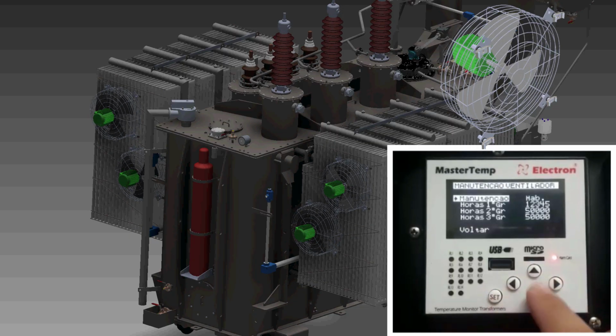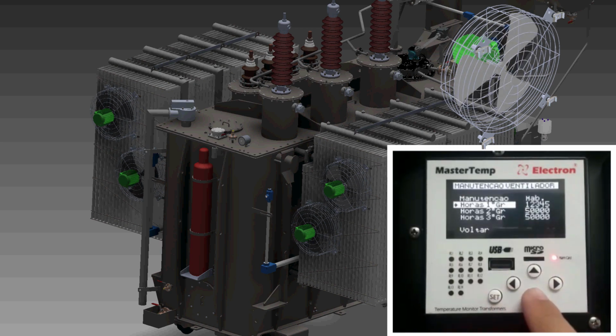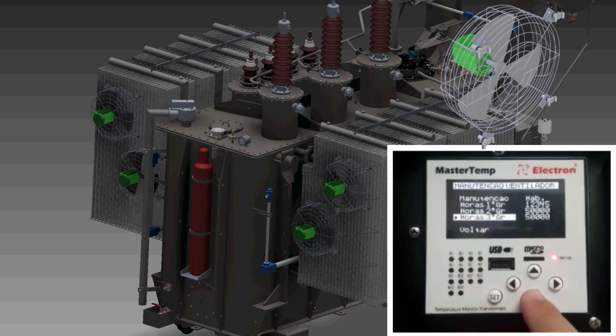Mastertemp also monitors the operating time of programmable alarm fan groups, which alerts the need for maintenance, when reaching the value of hours recommended by the manufacturer of ventilators.